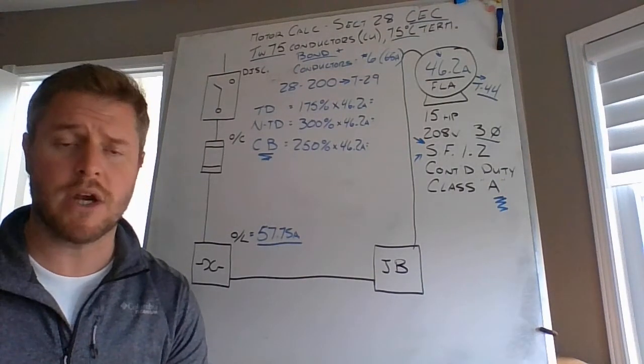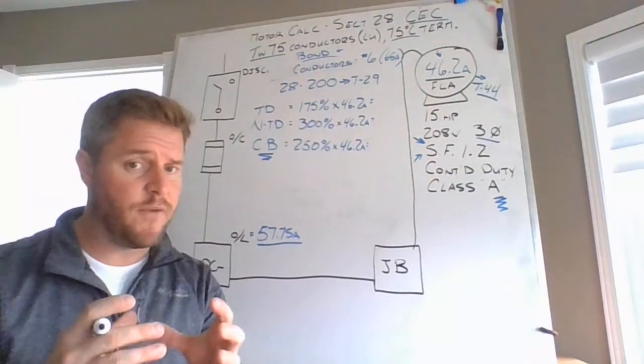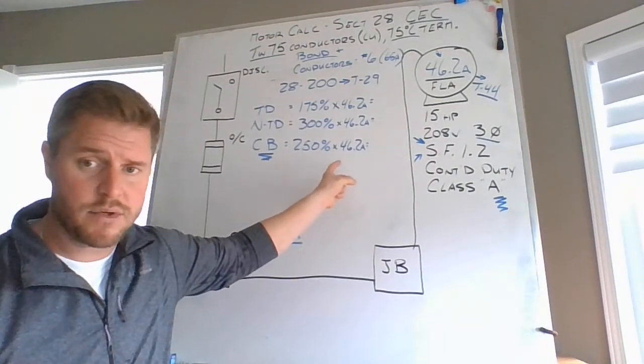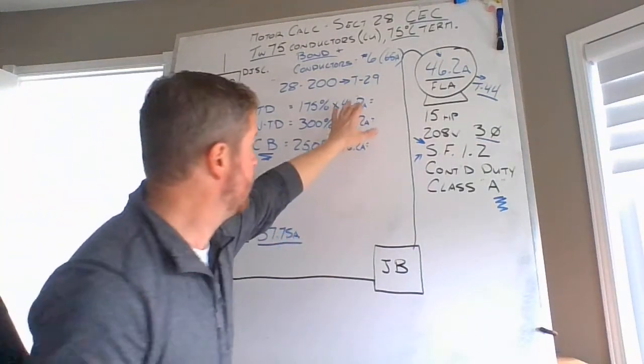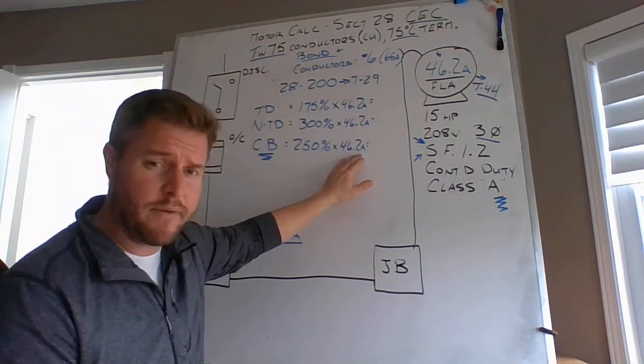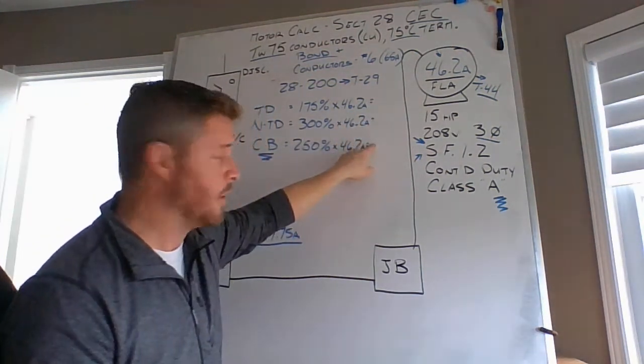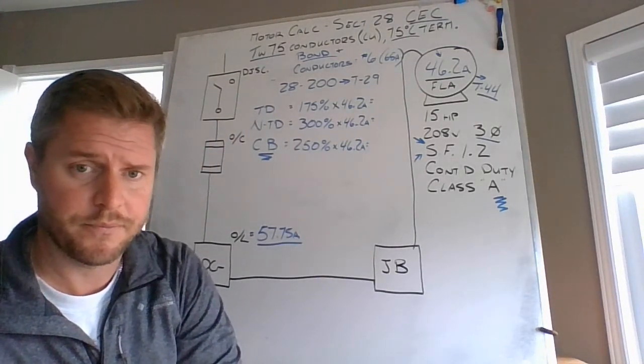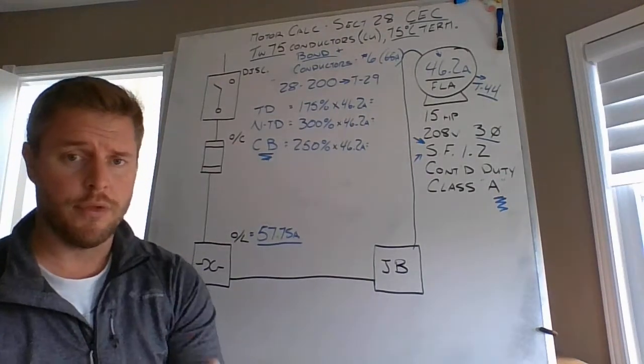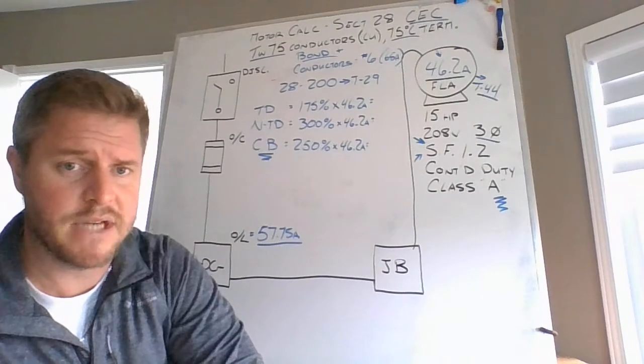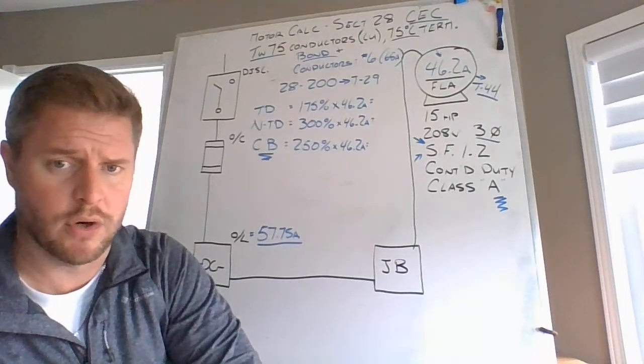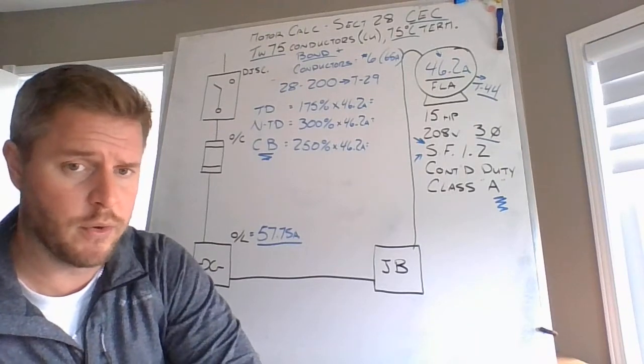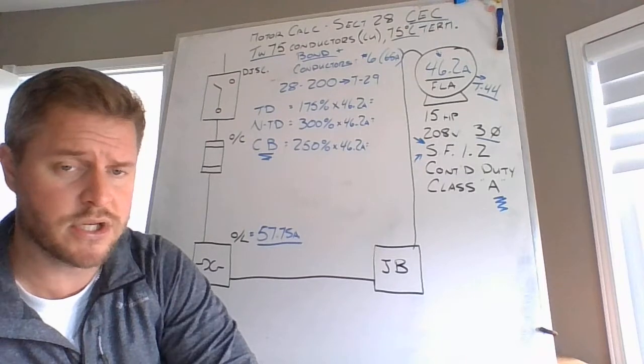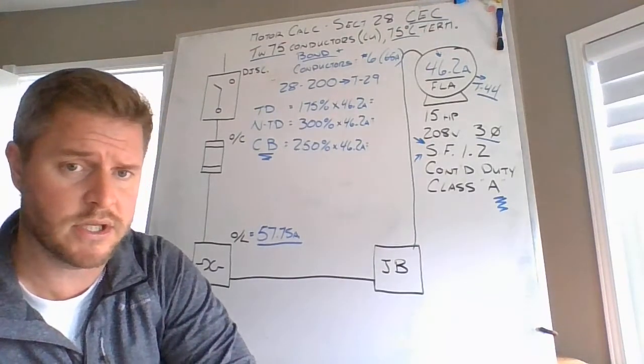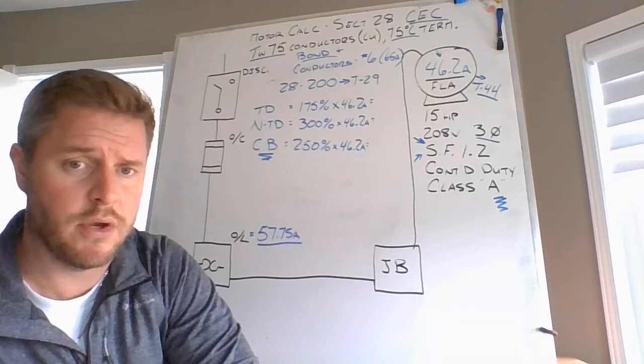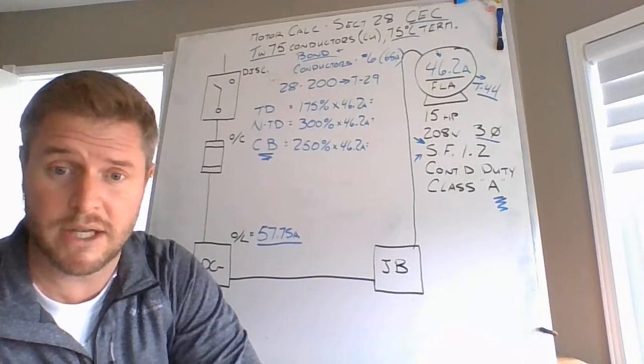Now, also, when you read through 28200, you will see, and it's very specific in the code book, that you cannot exceed these calculated values. Very specific in the code book. Once you go through and you do all these calculations for your 3 individual overcurrent devices, once you find those numbers, they cannot be exceeded. So go through 28200, observe table 29, look at your opportunities for overcurrent devices. Now will be a good time for you to hit pause on this video, go through and do those calculations with me. We'll do this together. I'll put the calculations on the board in just a second. But now will be a good time for you to pause this video so that you can come back and observe what's going on with this motor calculation.